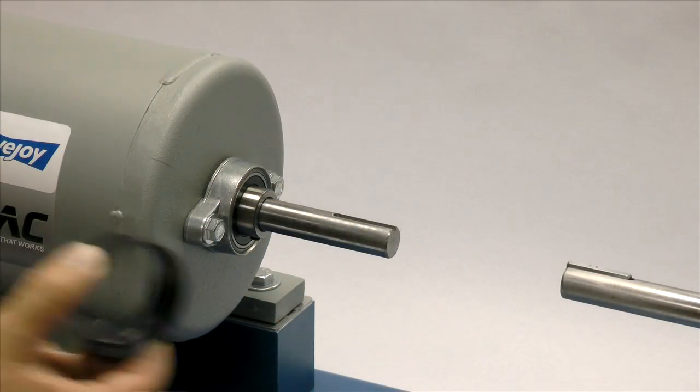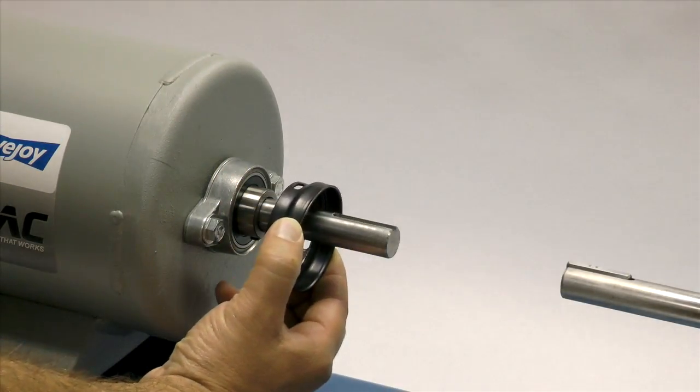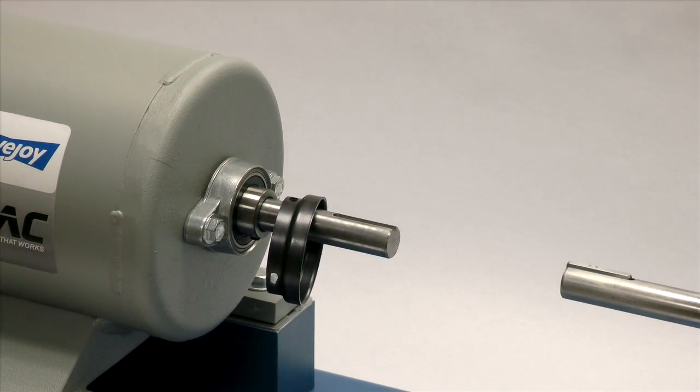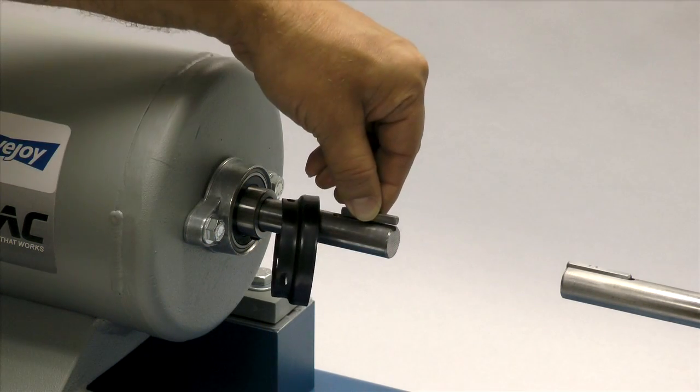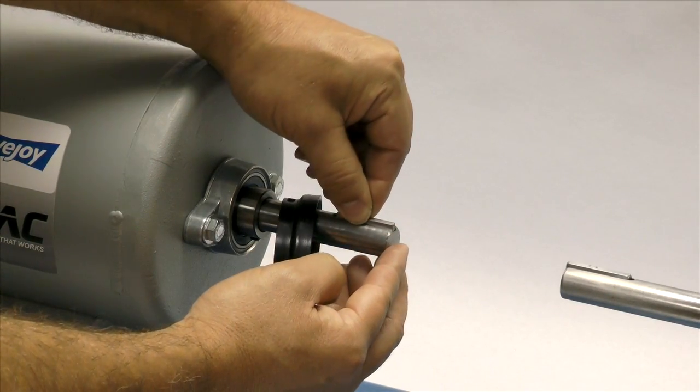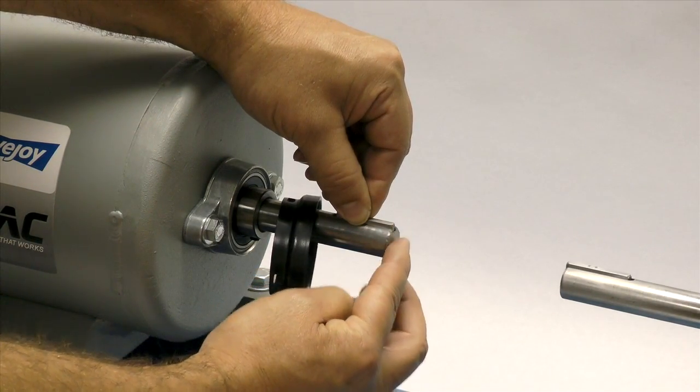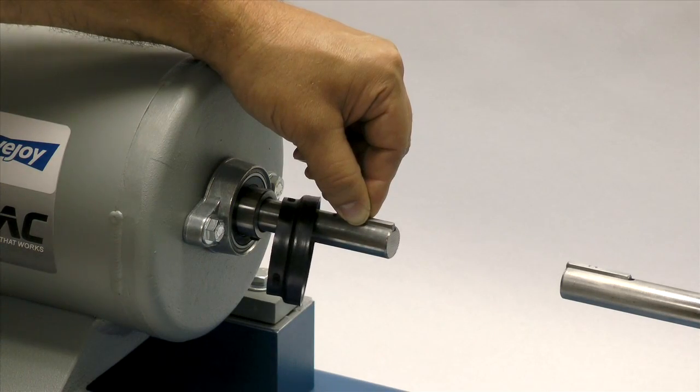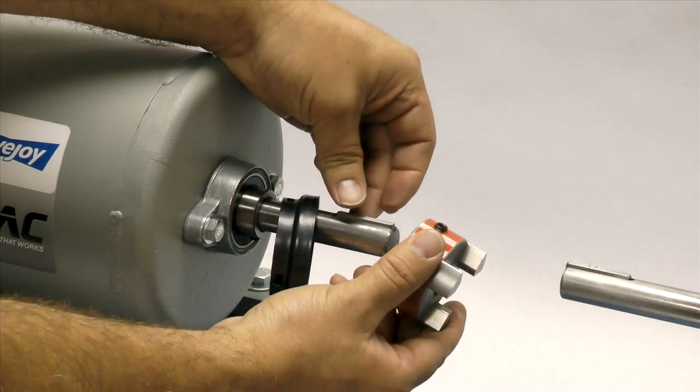Before installing the hub, slide the collar onto the shaft on the side where the LC style hub with the tapped holes will be mounted. Then place the key in the keyway on the shaft. The key should fit snugly into the keyway with no side-to-side movement. The end of the key should line up with the end of the shaft and the hub.